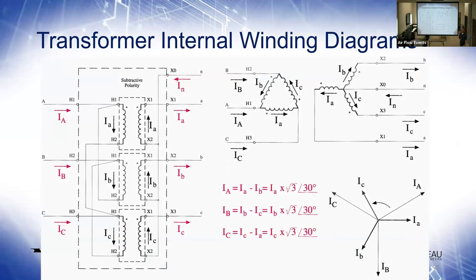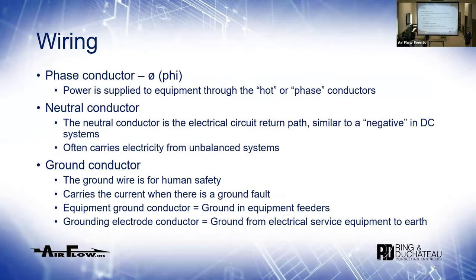I had an engineer designing a project out east who wanted some fan coils — small motors — and said they've all got to be 480 volt three phase. He said he didn't have 120. He probably didn't even know why. The thing about 120 is everybody uses 120 — we have receptacles all over. It made no sense to me. It was a third-horsepower motor; you want 480 three-phase for a third horsepower? That's unusual for that small. I'm guessing the distribution wasn't where he needed it to be. You can create anything at a price. So moving on to the wiring side of things.